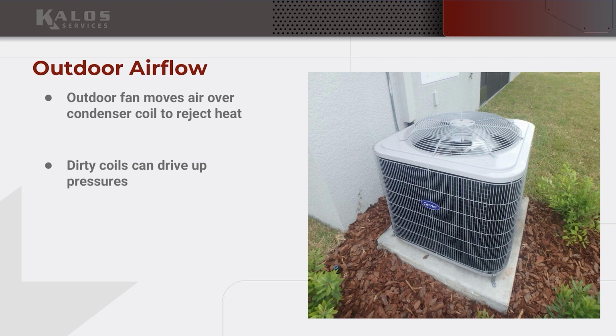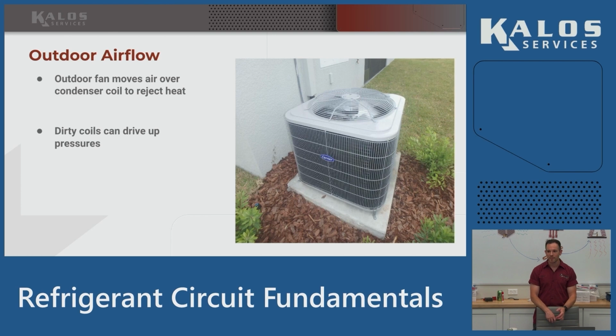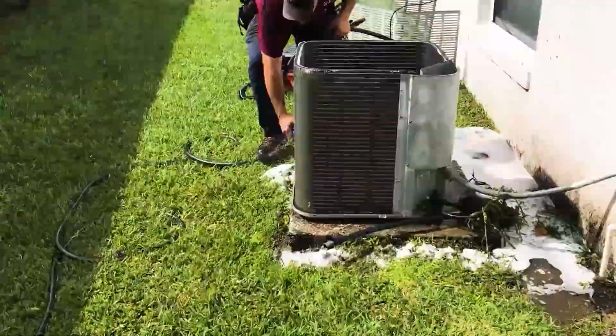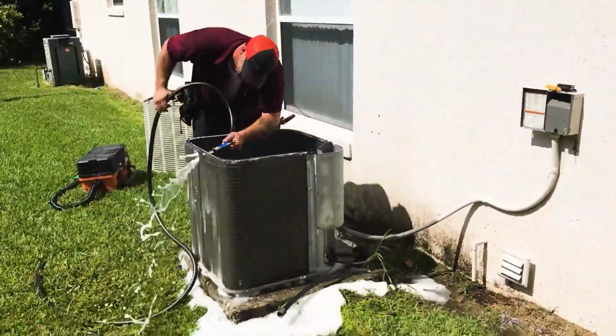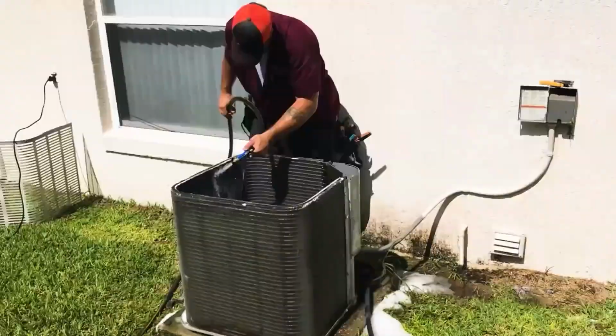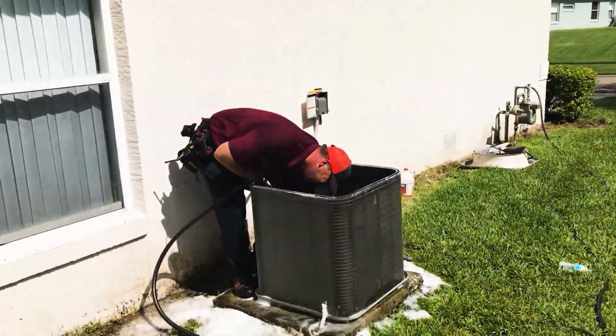And then we already talked about outdoor airflow, about what happens when we have a dirty coil. For the same reason, if I can't move airflow here and it's getting too cold, outside I'm gonna have the opposite problem. No airflow means it's gonna get really hot in there. You'll see the same problem if my outdoor fan motor dies. You'll watch your head pressure go through the roof because I'm no longer rejecting heat. It's just sitting there heating up my compressor. Eventually my compressor will go out on thermal overload. So you want to keep those coils clean. It improves efficiency and it keeps our pressures down so everything runs properly.